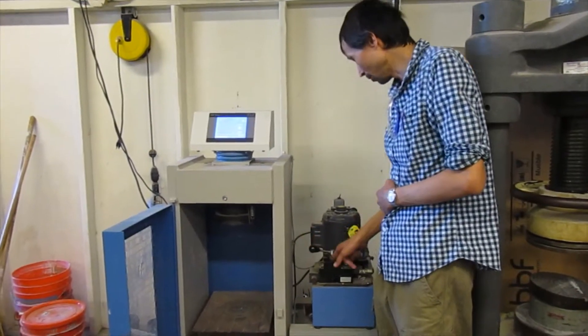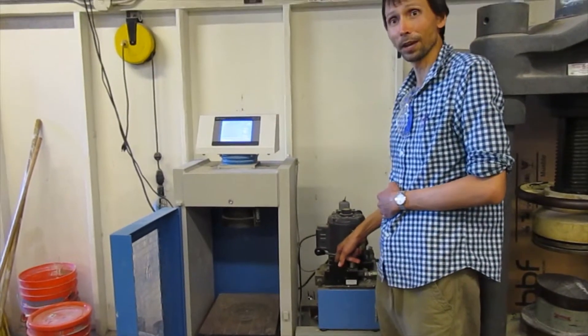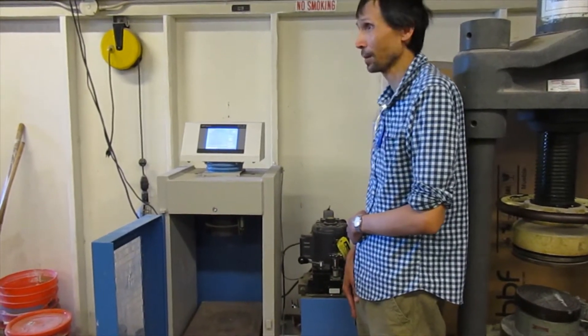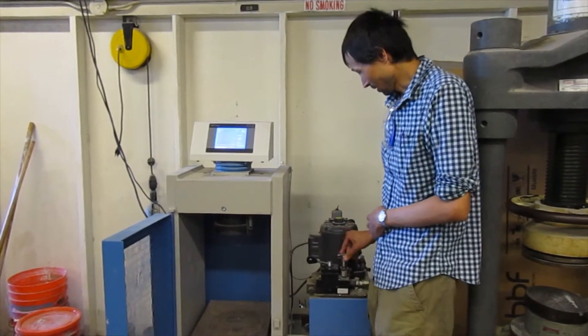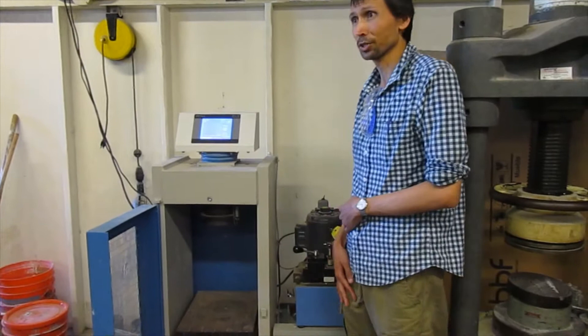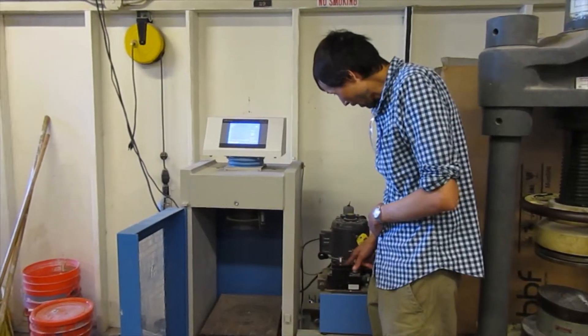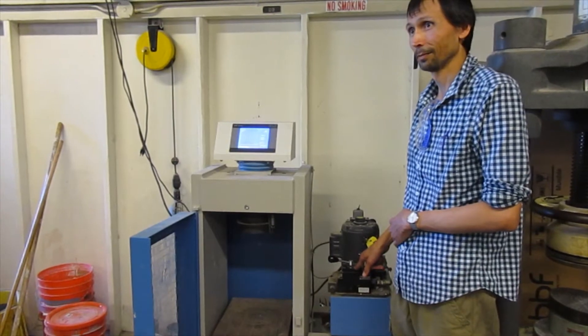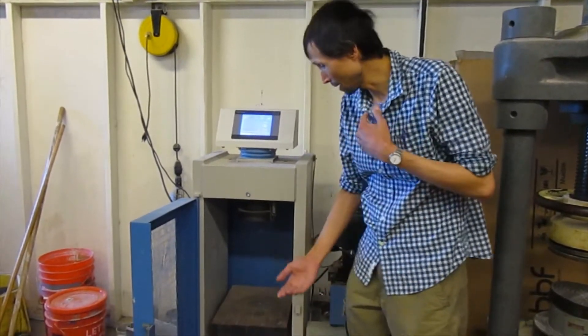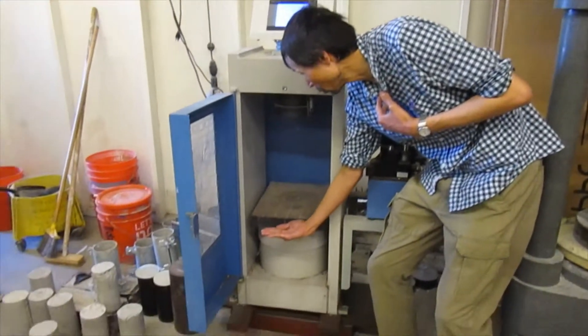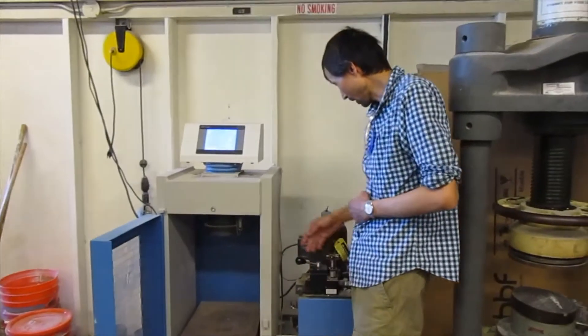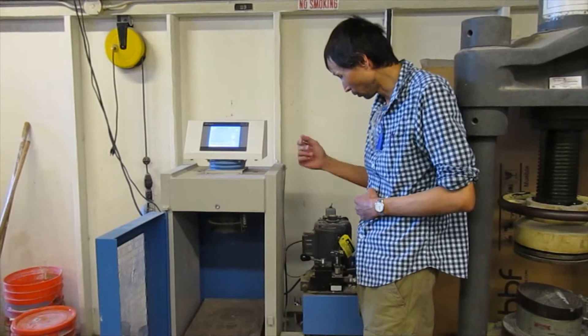And then it's got metered advance. You know what metered advance does? The test is ready to start and I'm going to load it at 1,000 pounds per second. And then I've got full advance. So full advance, what does that do? If I want to float the table, I'm moving the bottom ram up a little bit. So those are the settings. Retract, hold, metered advance, full advance.